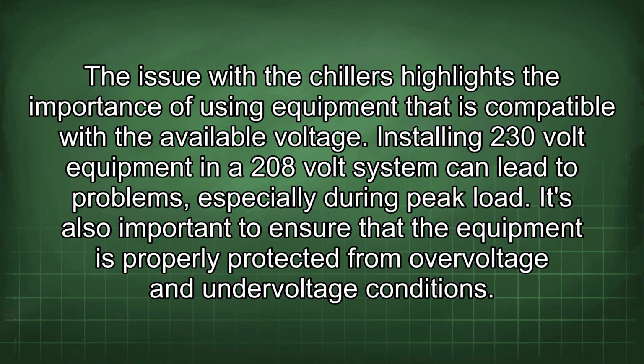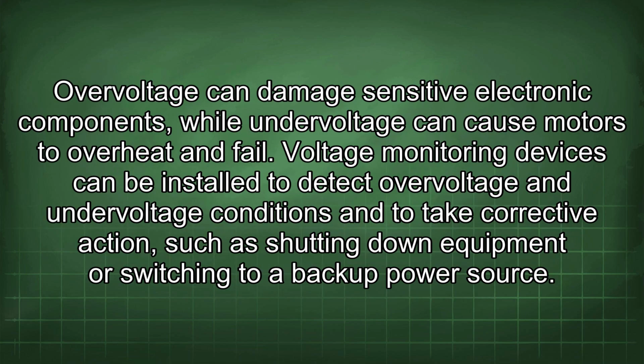It's also important to ensure that the equipment is properly protected from overvoltage and undervoltage conditions. Overvoltage can damage sensitive electronic components, while undervoltage can cause motors to overheat and fail. Voltage monitoring devices can be installed to detect overvoltage and undervoltage conditions and to take corrective action, such as shutting down equipment or switching to a backup power source.